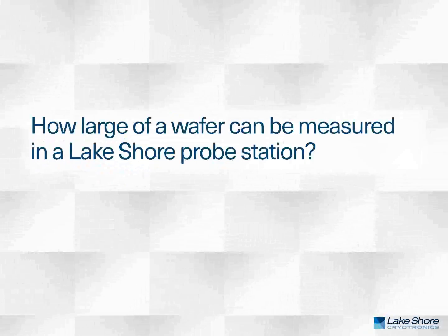It's a really good question. So in our standard configuration of probe station, the largest size is a 4-inch wafer. Now with some concessions in your probing area and thermal performance of the probe station, we can accommodate larger wafers up to about 6 inches.